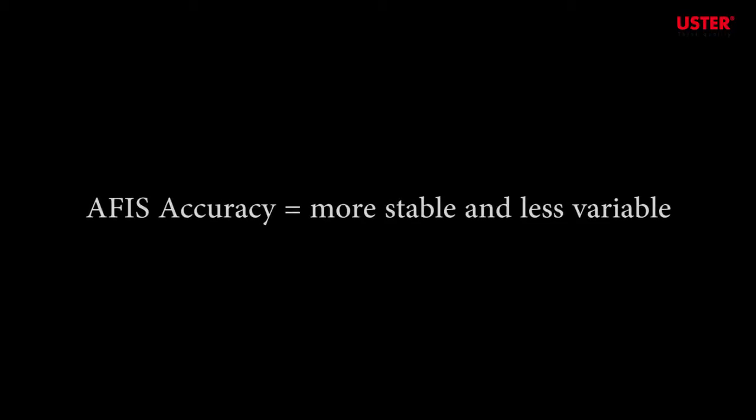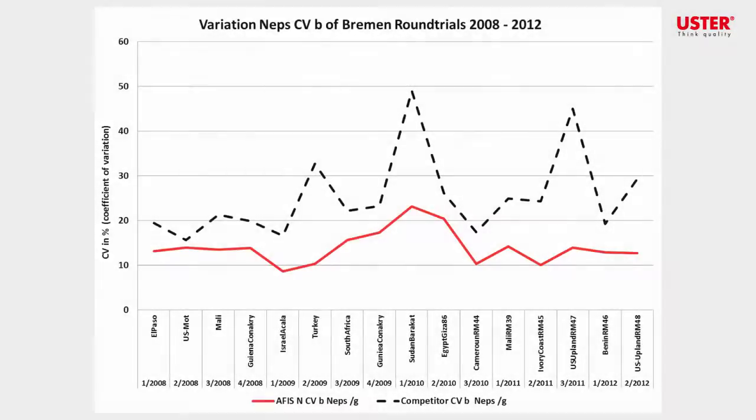Bremen round trials, covering the latest Uster AFIS Pro 2 instrument, enable comparisons with the competitive product. The trials include over 50 laboratories using AFIS and about 10 using the competitive product. NEP content is the first quality parameter covered in the trials. For AFIS, the results show fairly stable variations in NEP measurement, while the competitive instrument shows high variation in data.